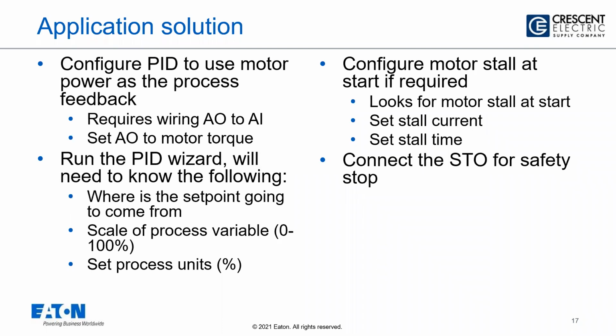And there is a feature to protect the motor and the drive if there is a motor stall. The drive senses if the motor stalls at a stall current that is presettable for a duration, and it can either give you a flag or stop the motor. So you can free up the impeller, make sure everything is okay, then restart the motor. And you can connect the safe torque off, or safety stop, so that as per the STO standards, the drive disconnects and protects anybody who is going to troubleshoot and work on the motor.